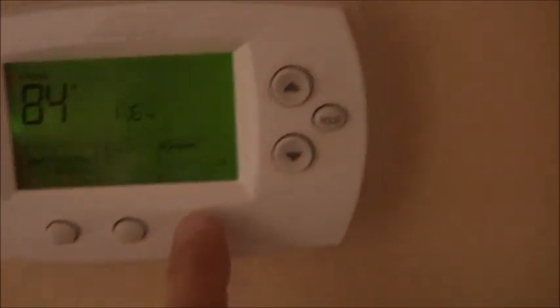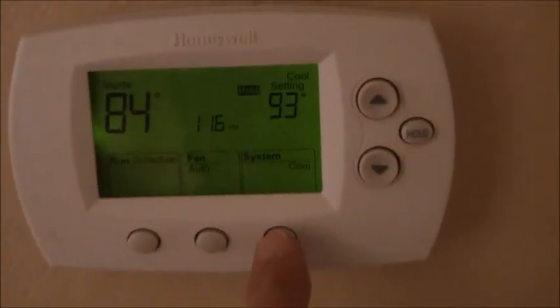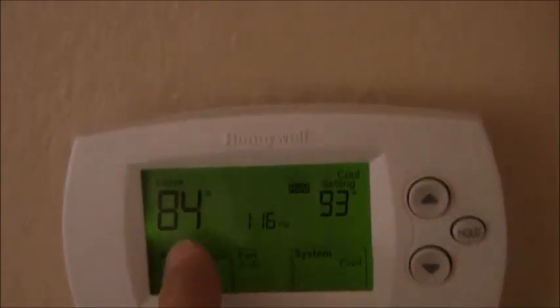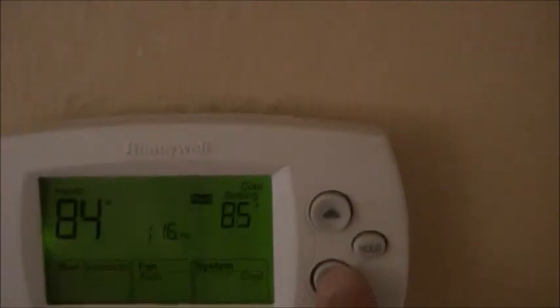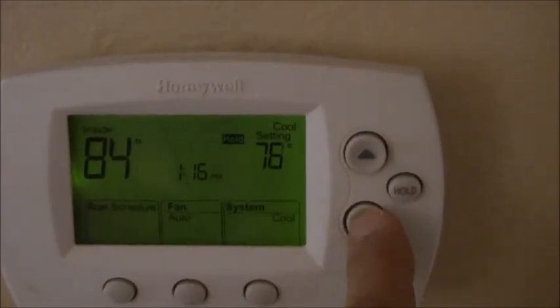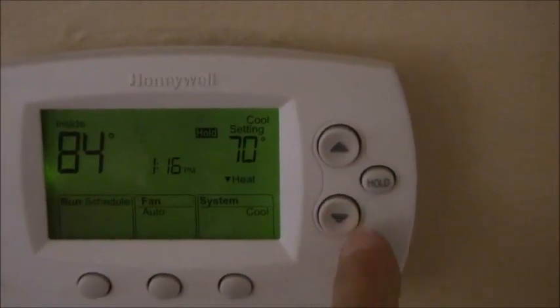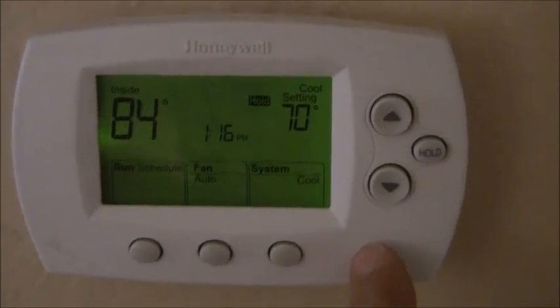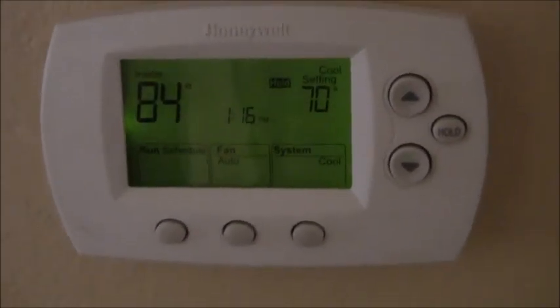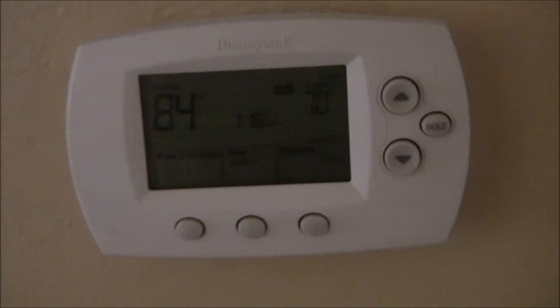Okay, we're inside, back at the thermostat. We're going to go to system cooling. Hit the mode button, go to system cooling. The house is currently 84 degrees. We're going to drop that down to 70, and that will kick off the cooling. So the fan should start up any second now. I could just hear the fan. Let's go see if the compressor started outside.